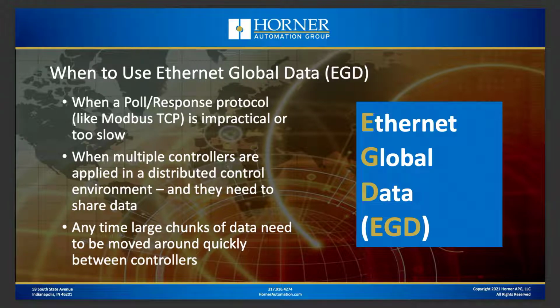You know, a few seconds is fine for SCADA maybe, but it's not going to work for an application with multiple controllers where you need to do distributed control, for instance. And let's talk about distributed control. When you're using multiple controllers in a distributed control environment and they need to share data, sometimes large chunks of data, that's the other scenario where EGD works great.